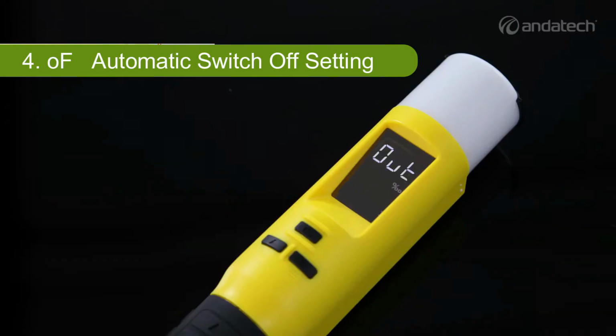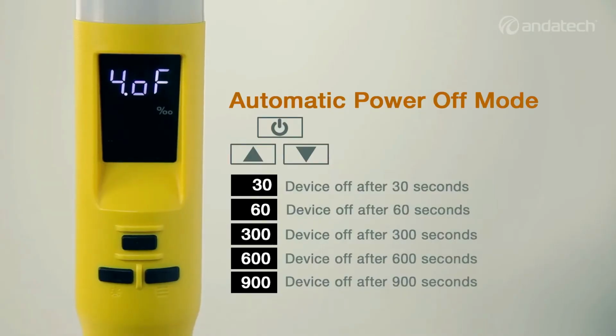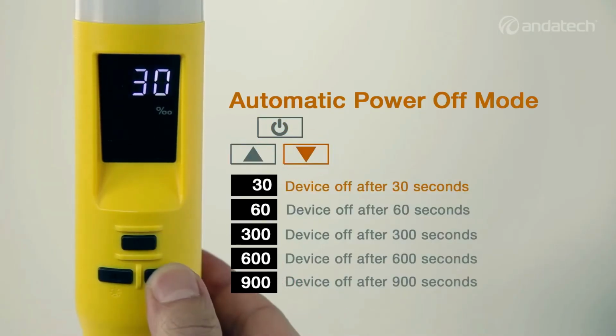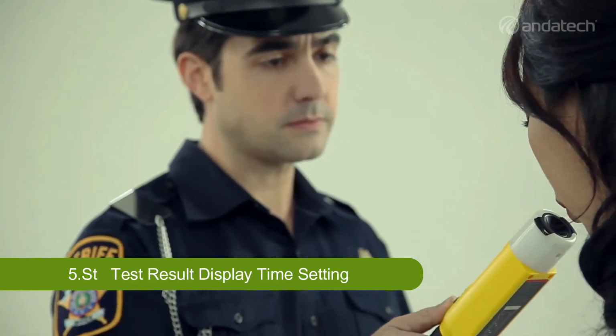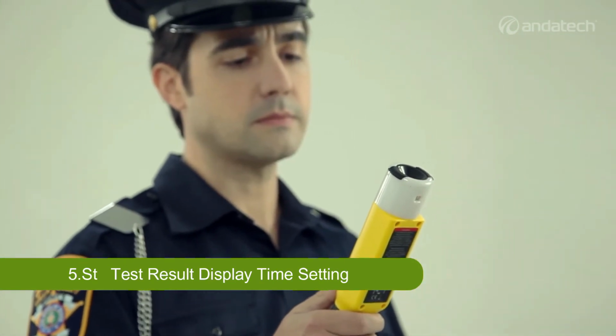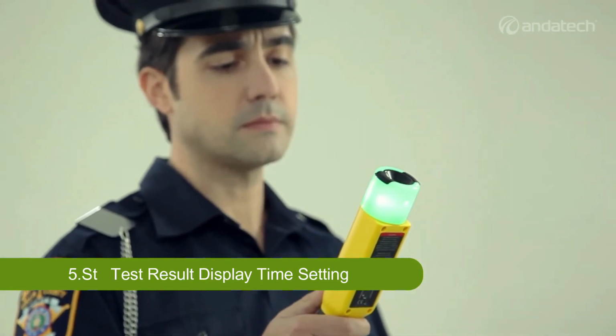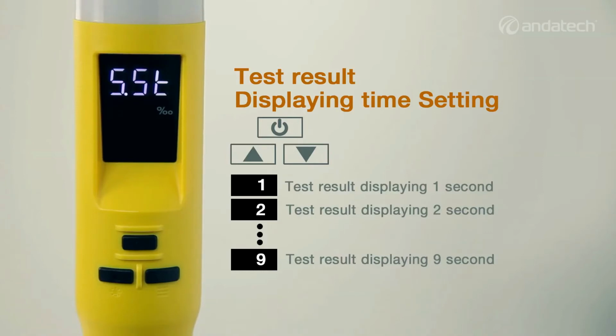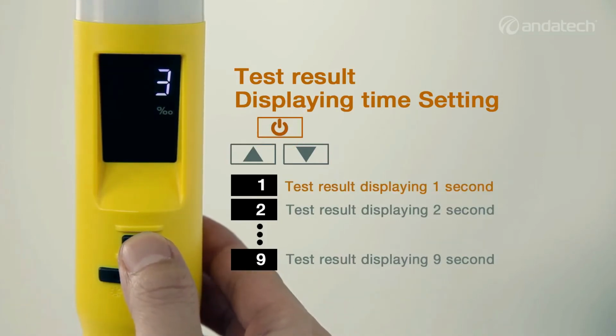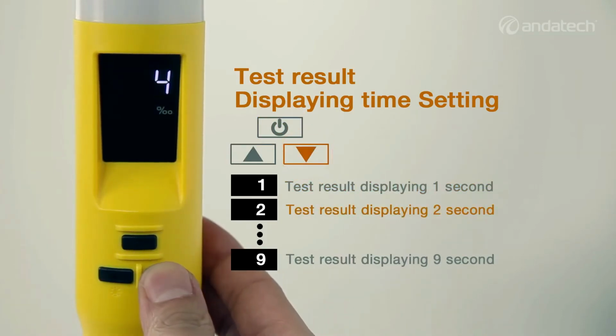4OF is the automatic power off mode. The timer can be adjusted to 30, 60, 300, 600, or 900 seconds. 5ST is the setting mode for the duration time of the test result that will be indicated on the display. The duration time of the test result to be indicated on the display can be adjusted, 1 second at a time, for up to 9 seconds.